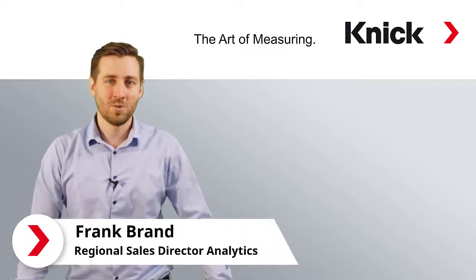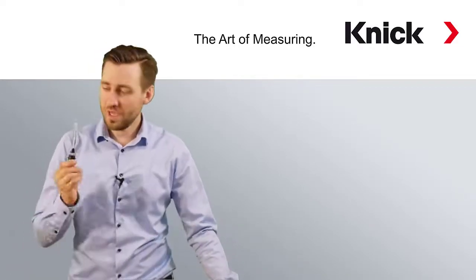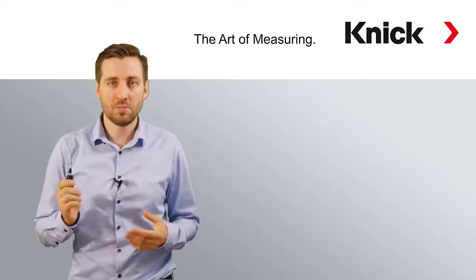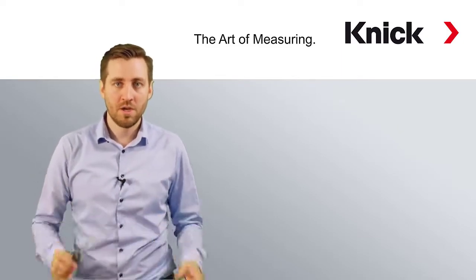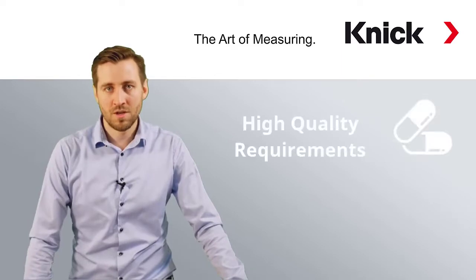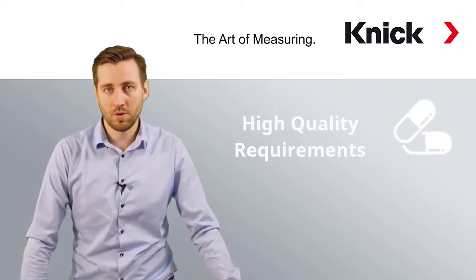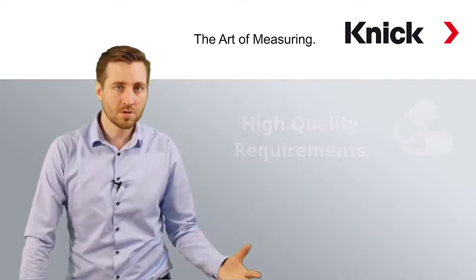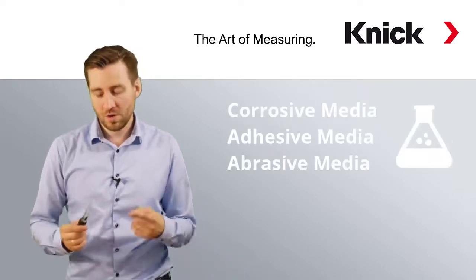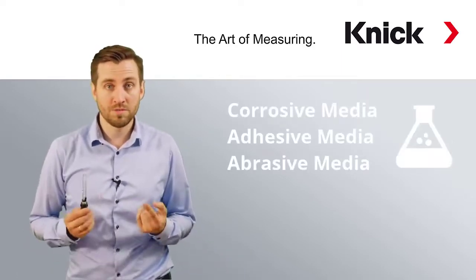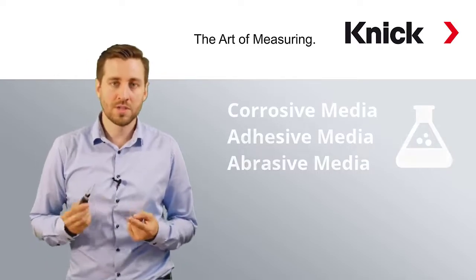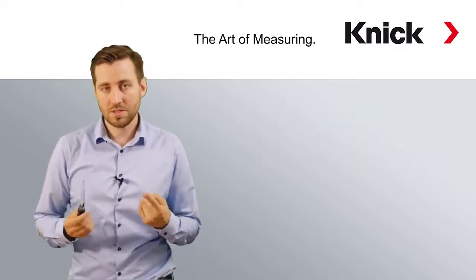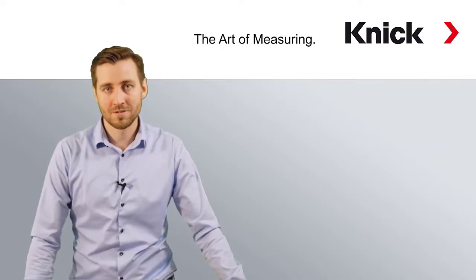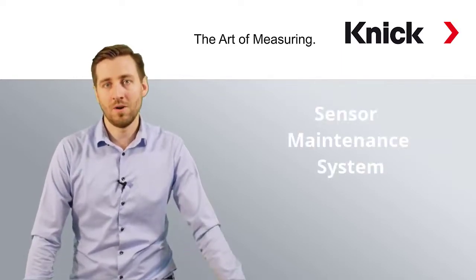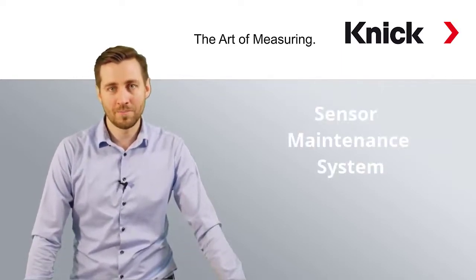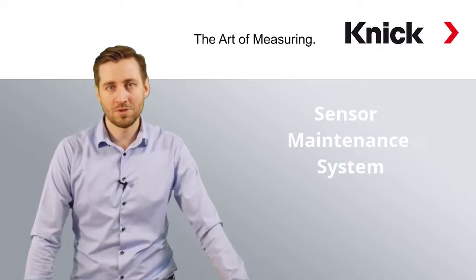In quite a lot of industrial processes, pH sensors have to be cleaned and recalibrated several times per day. For example, in the pharmaceutical industry, as we have very high quality requirements here. In the chemical industry, we face a lot of corrosive, adhesive or abrasive media, so that we have to clean the sensor quite often so that we can still ensure accurate readings. So let me introduce to you our automatic calibration and cleaning system so that you can benefit from the features.